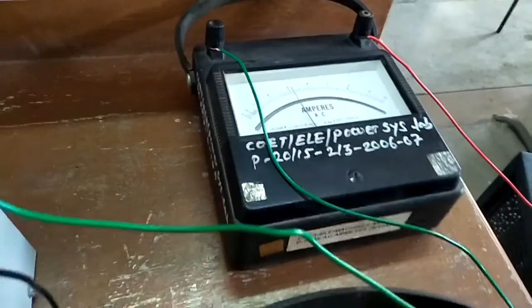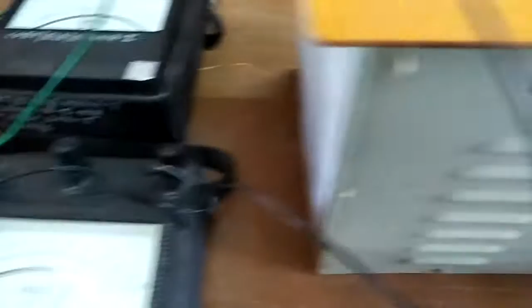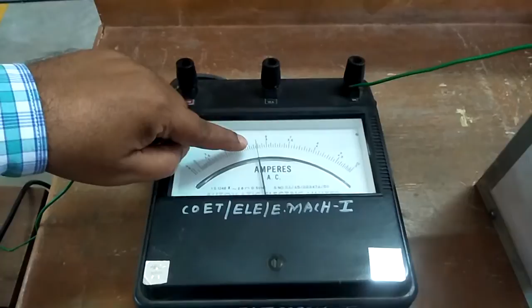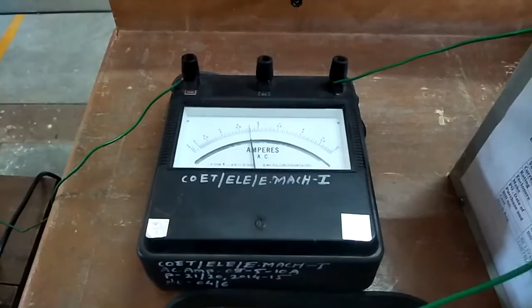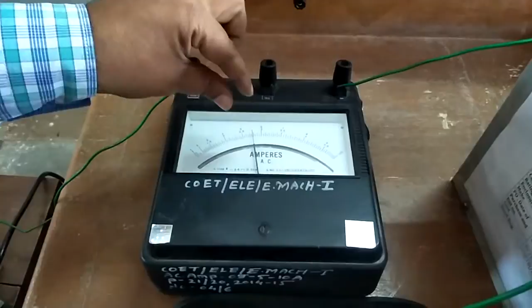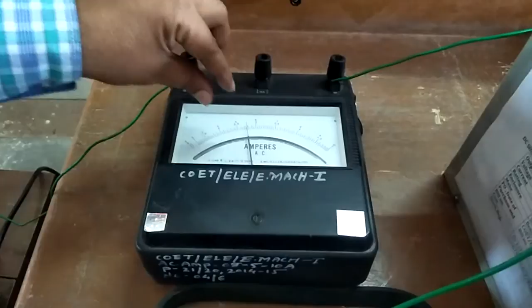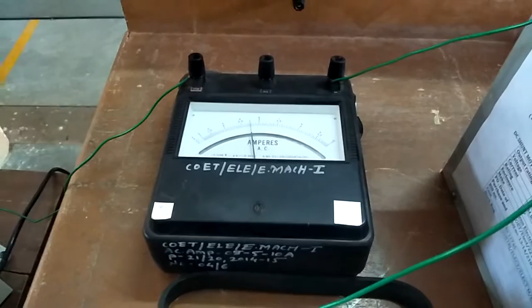Similarly, I will increase the load again. The current is around 5 ampere, whereas the primary current is 2.7 ampere. It should be double, so around 5 point something should be there, but because of the no load exciting current of 0.25 ampere, if you subtract this, it becomes 2.5, whereas the secondary current is 5 ampere.